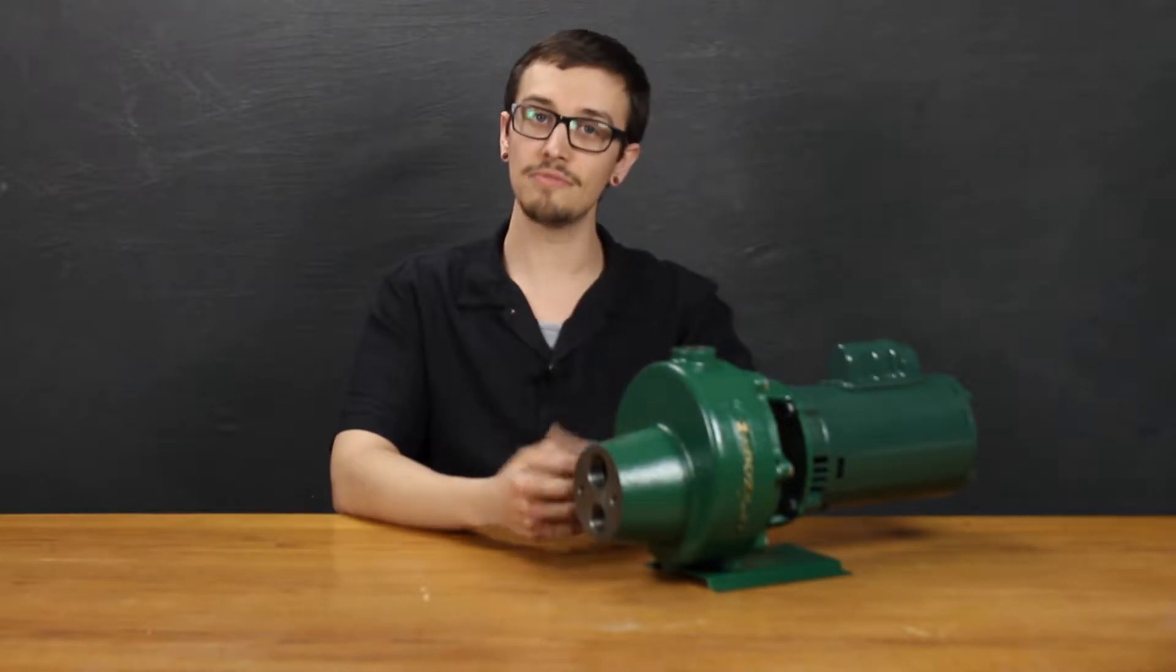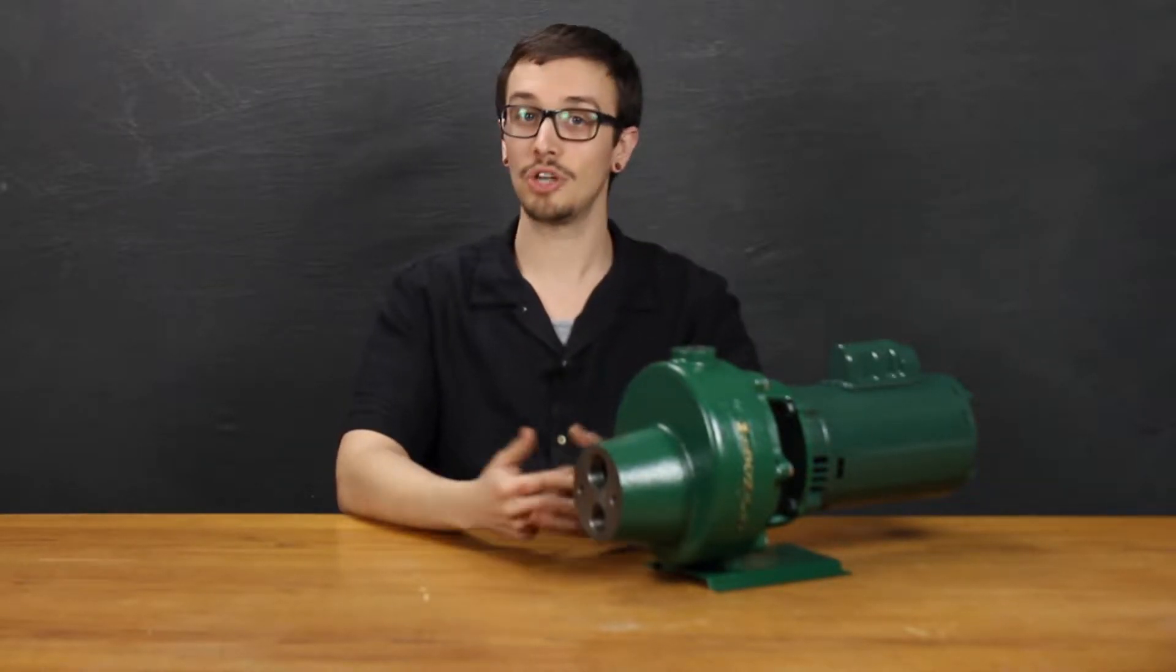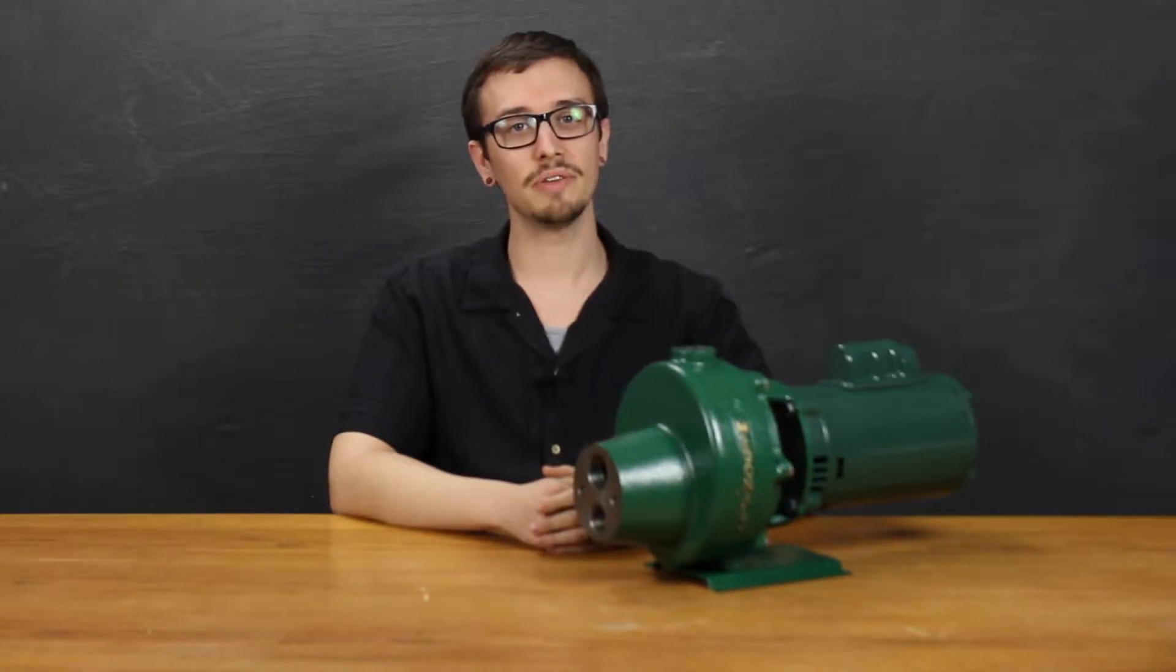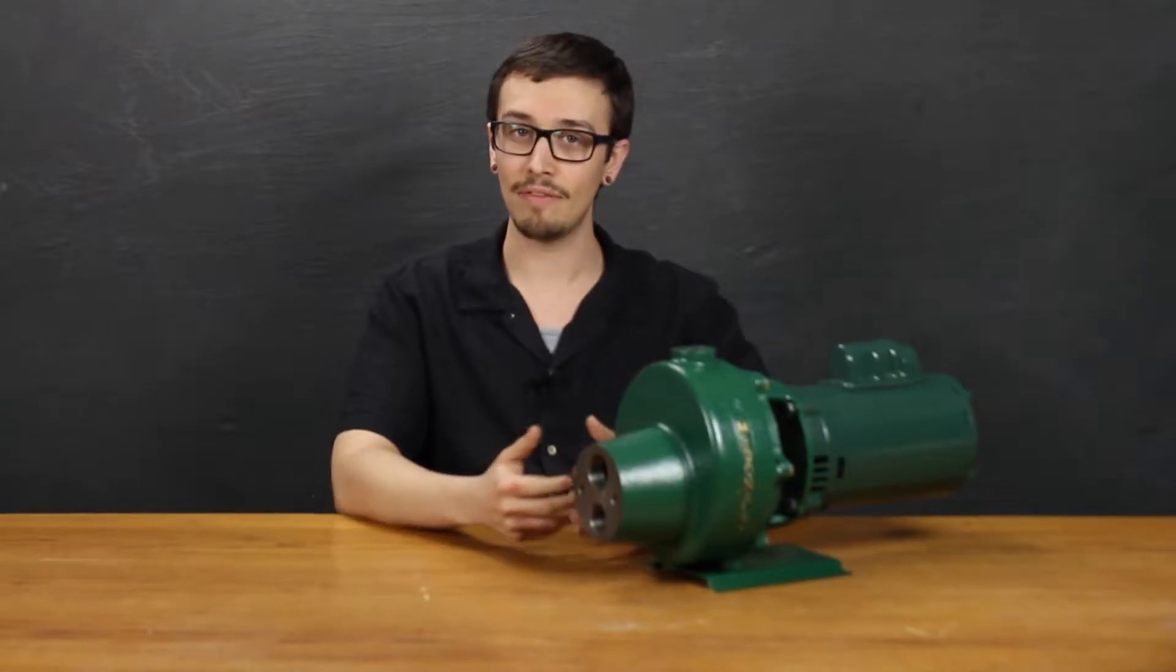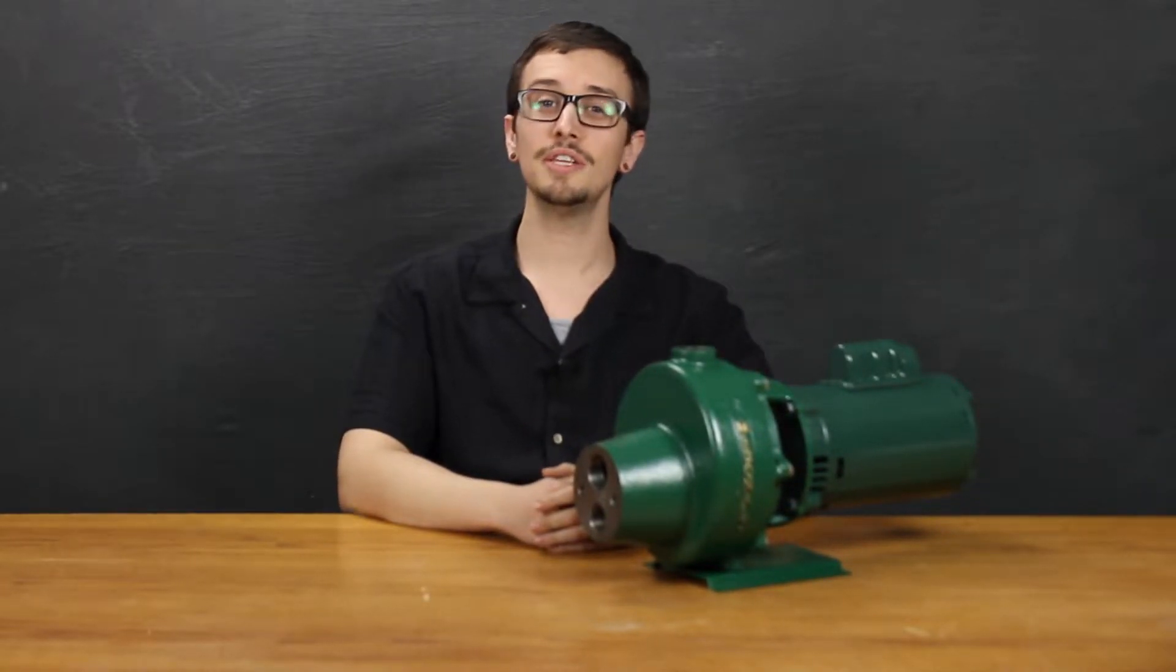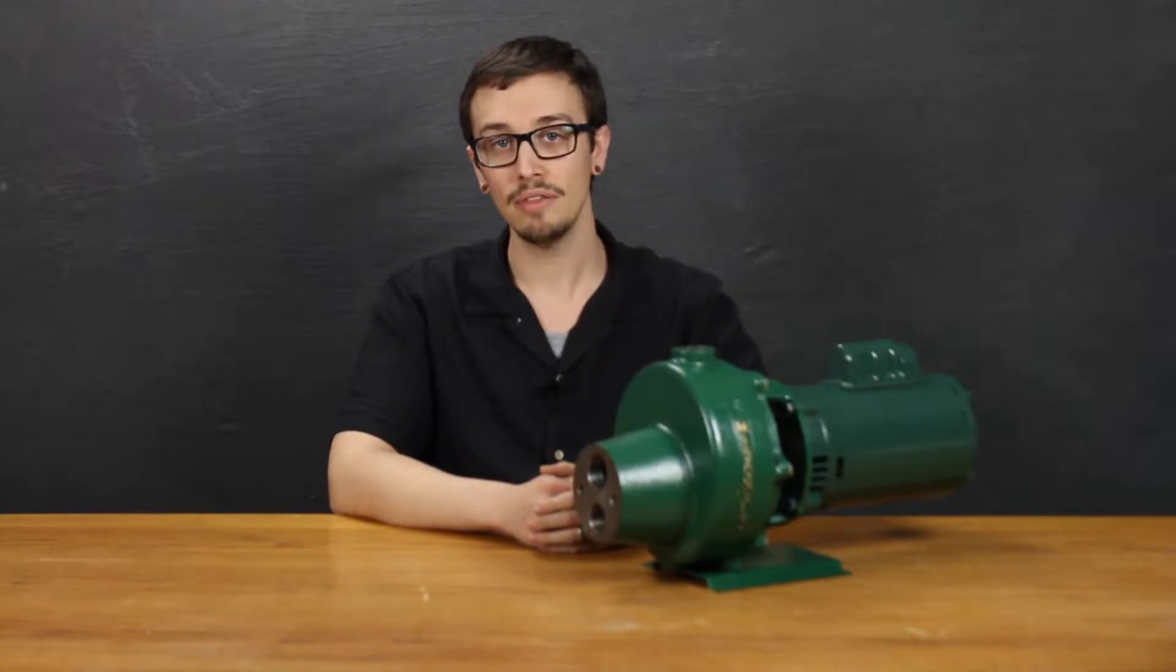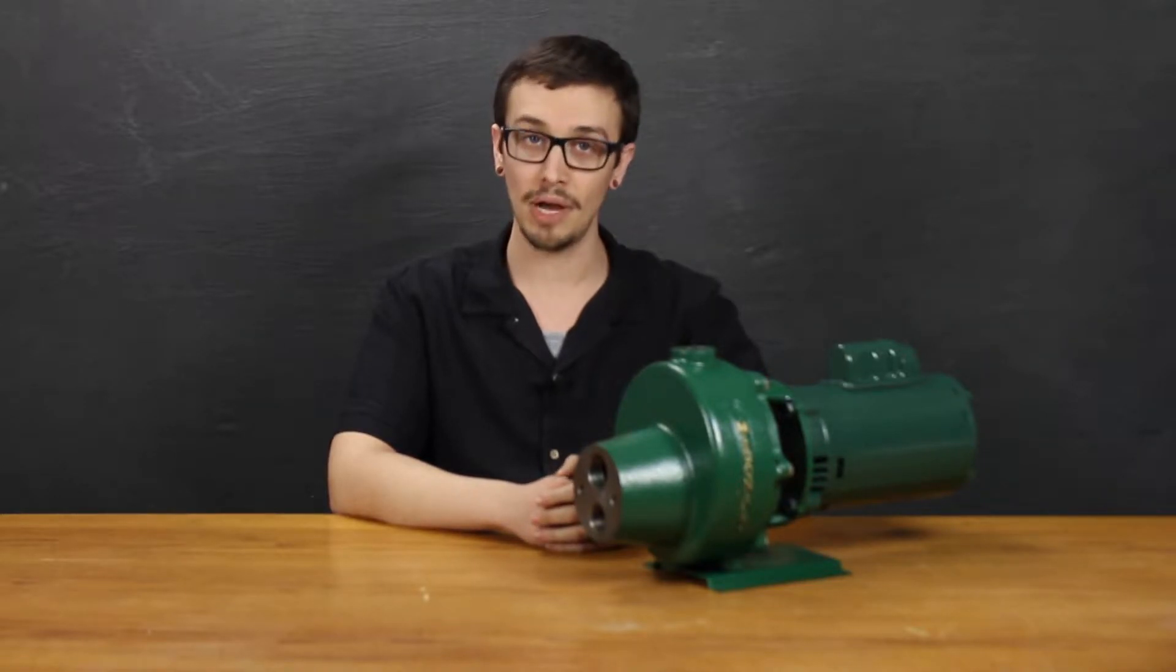It is intended for deep well only. The SW models or shallow well variants do not come with this valve. The 1500 series comes standard with a maximum suction lift of 25 feet. However, with the addition of a deep well ejector kit, these pumps can lift an astonishing 160 feet. This is accomplished by installing a jet ejector down the well piping.